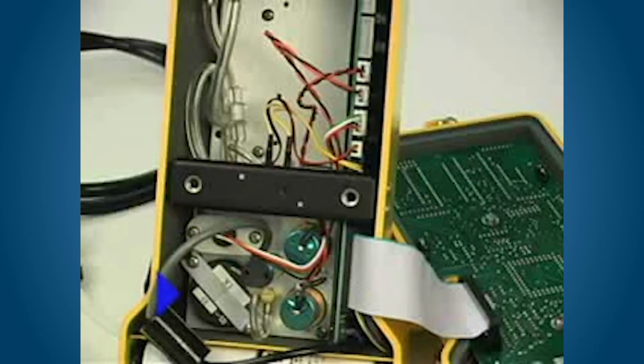The oxygen sensor is mounted face down in the sensor block to allow the sample flow to diffuse into the sensor. A multi-pin plug connects the oxygen sensor into the CN2 socket on the analog PCB. The carbon monoxide and hydrogen sulfide sensors are physically very similar. They both have cylindrical bodies and are mounted face down in the sensor block. A 3-position connector from each sensor plugs into EC1 or EC2 sockets on the analog PCB. The sensor connected to the EC1 socket displays as channel 3, and the sensor connected to the EC2 socket displays as channel 4.